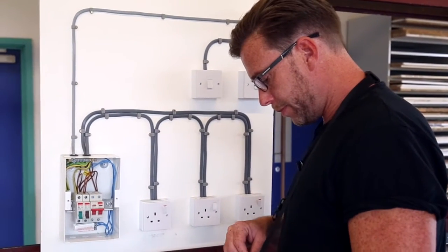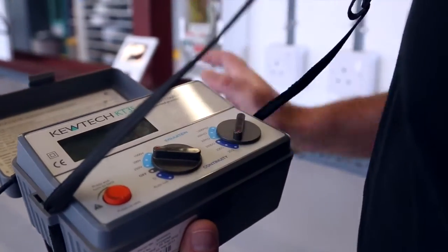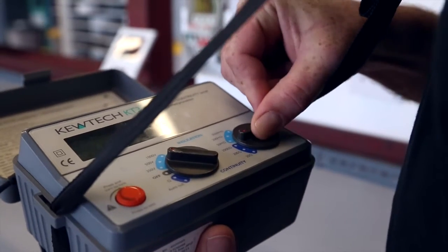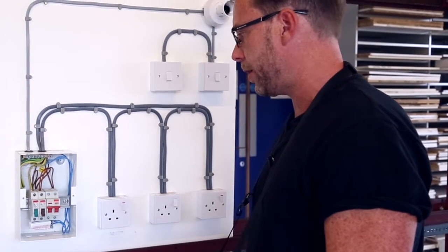So now we're going to set up the meter. We're going to place our first dial onto 500 volts and our second dial onto 200 megaohms. But this time we're not going to use the auto lock function.